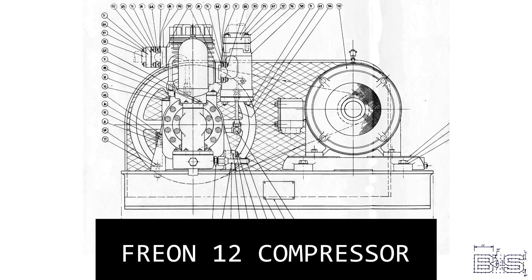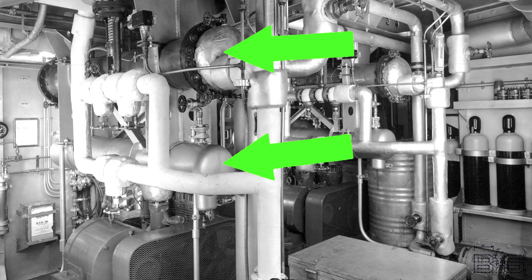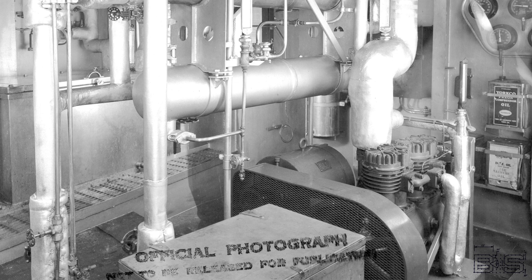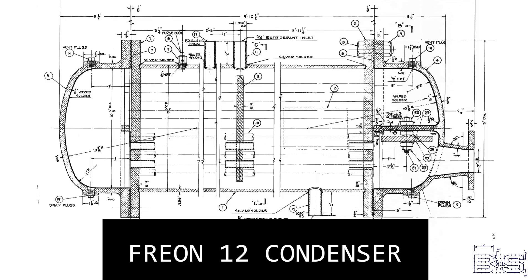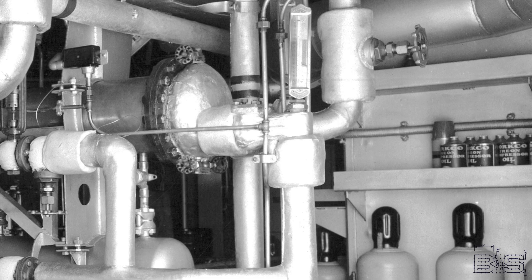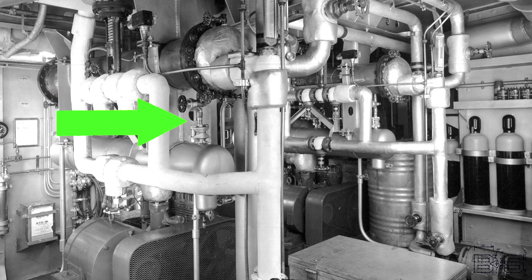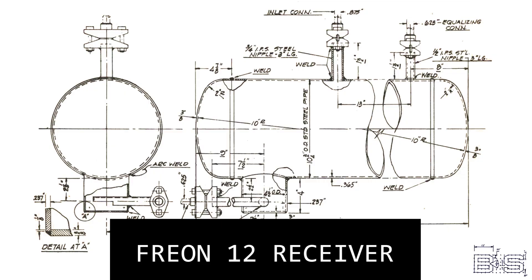But the refrigeration plant would just be a bunch of pipes and valves if it weren't for the compressors. These are four-cylinder single-acting belt-driven reciprocating compressors. Mounted above every compressor is a condenser and accumulator duo. After the Freon is compressed into a hot gas, it enters the condenser — a seven-foot long brass tube filled with smaller tubes that carry water to cool the refrigerant. Seawater is pumped through these condensers and then discharged overboard. After the Freon leaves the condenser, it enters the receiver as a liquid, which is just a reservoir to make sure there is enough Freon available to handle any load.